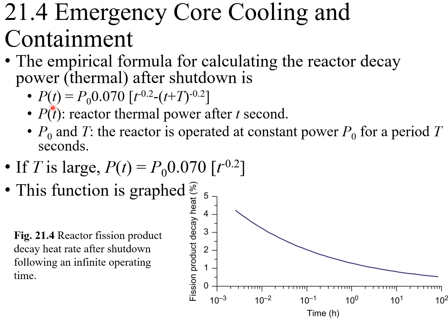In this formula, P(t) is the reactor thermal power after t seconds. So if you want to estimate, for example, 1 hour after shutdown, then this t will be equal to 3600 seconds. P0 is the reactor power before shutdown. If you operate this reactor at a higher power before shutdown, then at a later time after the shutdown you also get higher power, because more fission product was produced. And the capital T is the reactor operating time before the shutdown. Both the lowercase t and the capital T are in units of seconds.